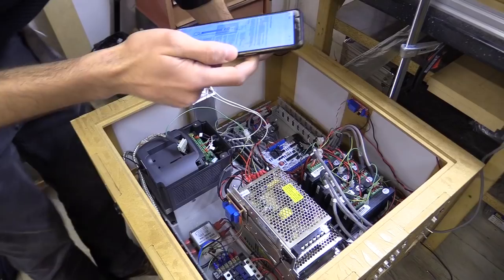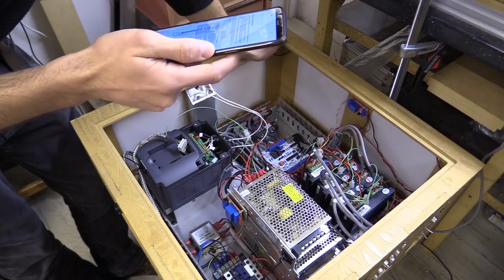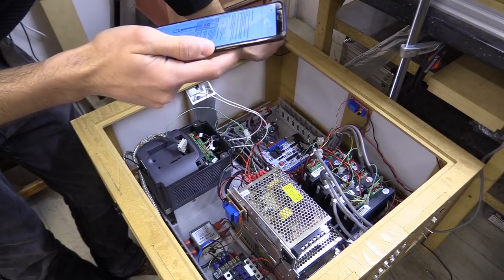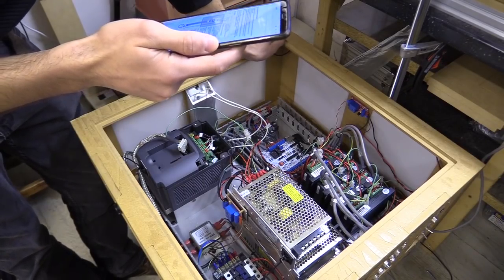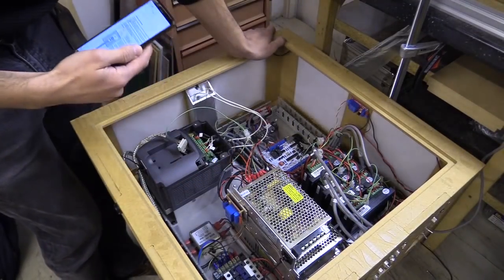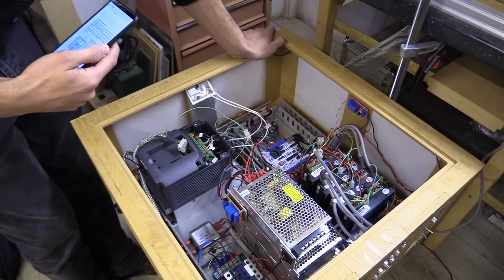These connectors should be as short as possible. Motor cables and signal lines of other control equipment should be at least 30cm apart. So there's lots of information in this actual manual that I can interpret, which is illustrating lots of things I should rethink about.